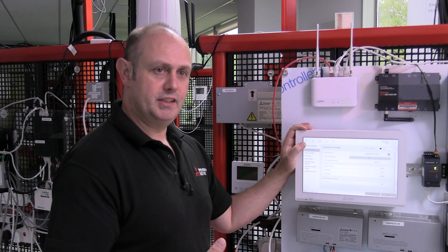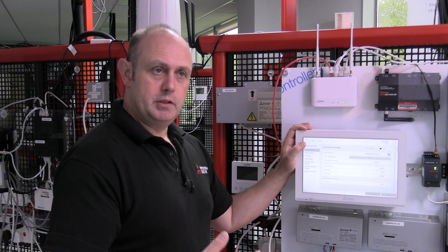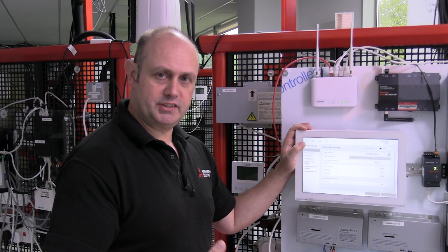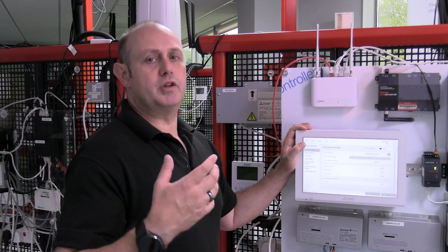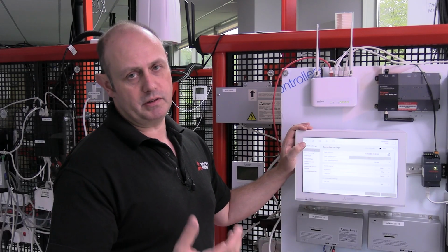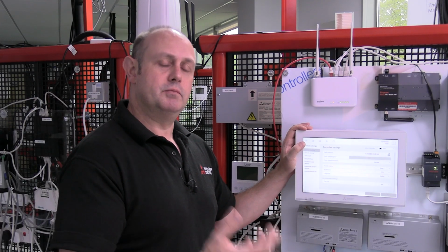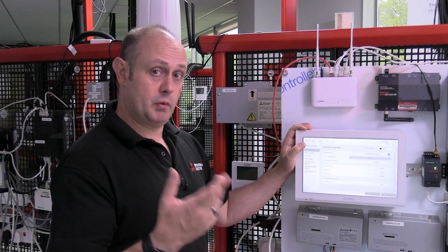One of the first things I want to play about with here, because I want to see the indoor units, is I'm going to go into groups, because the centralized controller won't populate itself. You need to tell it which indoor units are actually on this centralized controller. The reason being is, we could have multiple centralized controls in the building for, say, different tenants, potentially off the same system. So that's why we do it that way.